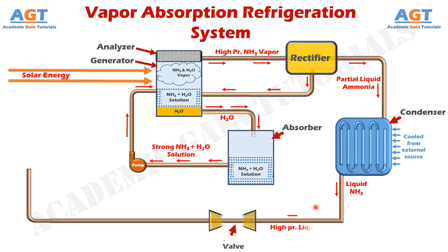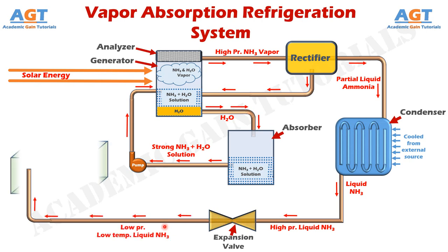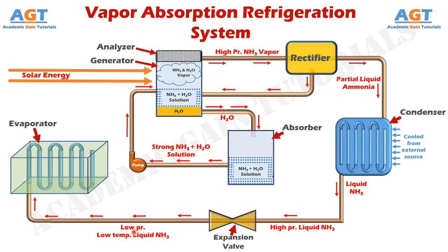Now, here we have an expansion valve. After condensation, liquid ammonia will leave the condenser and pass through this expansion valve. This high pressure liquid ammonia coming from the condenser will be expanded inside this expansion valve. We know that when expansion occurs, the pressure between the molecules decreases considerably, thus the temperature falls. So, this high pressure liquid ammonia will be expanded into low pressure, low temperature liquid ammonia. Thus, here we get very cold, chilled, low temperature liquid ammonia coming out of the expansion valve.